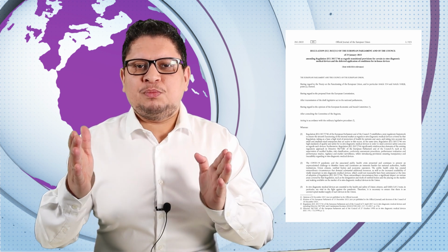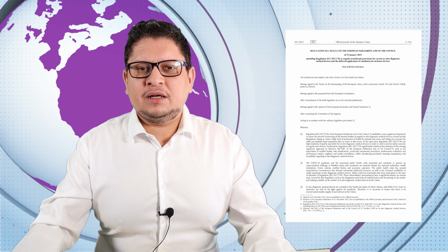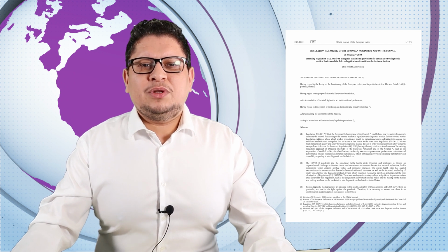During this transition period, it is also important that you follow the requirements of EU IVDR for post-marketing surveillance, for vigilance reporting, for market surveillance, and for economic operator registration. All of this you should follow, and you should even have a PRRC during this period. So there are a lot of things to understand here. Please don't hesitate to read this update of the regulation to really understand the dates. I know the dates seem a bit complicated because there are a lot of classes and a lot of changes, but it is really important to understand.